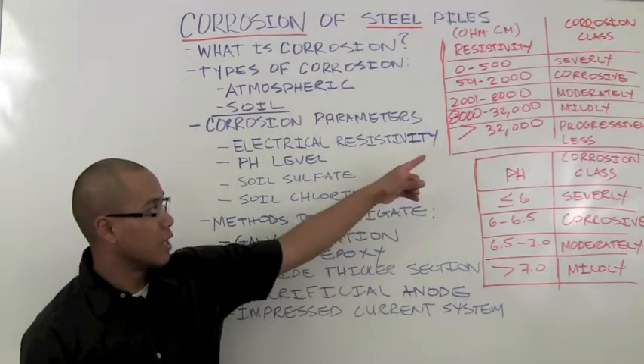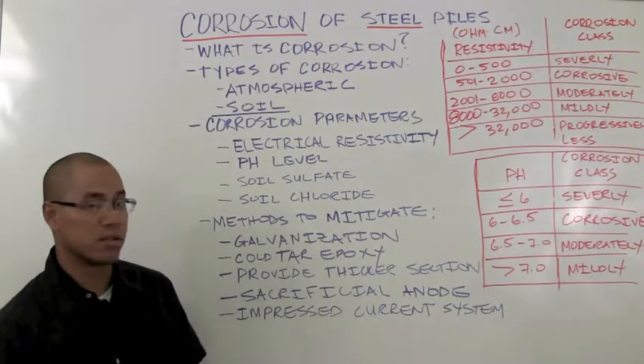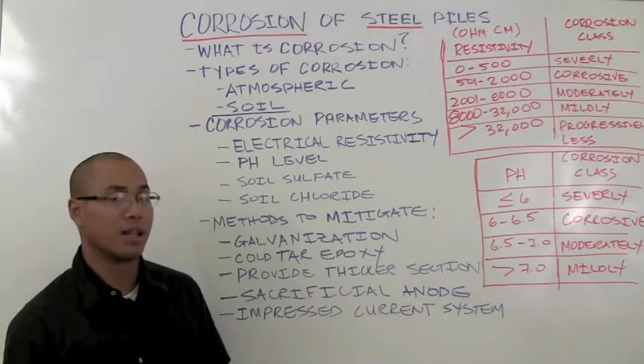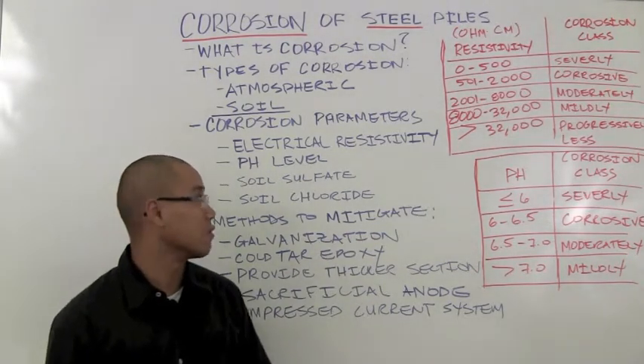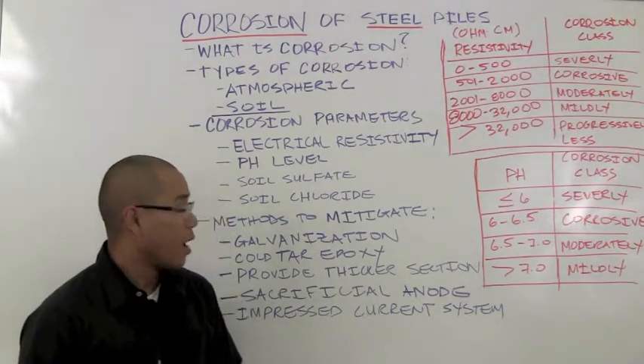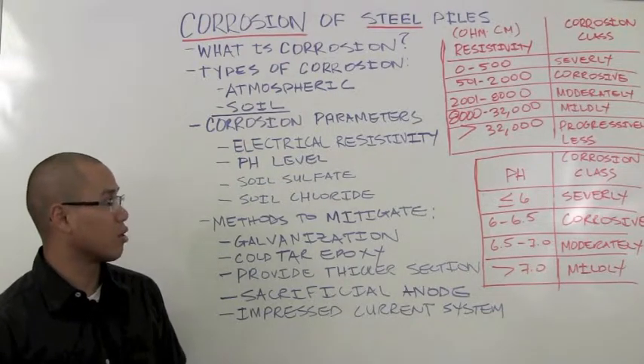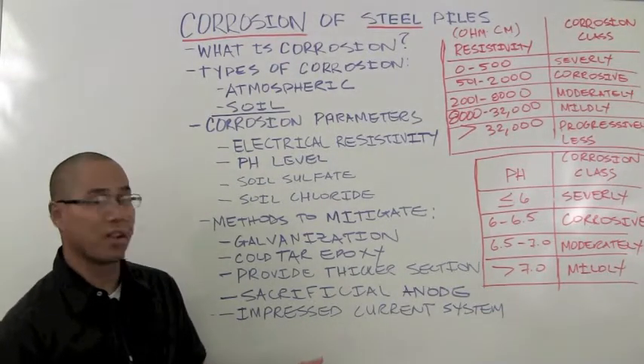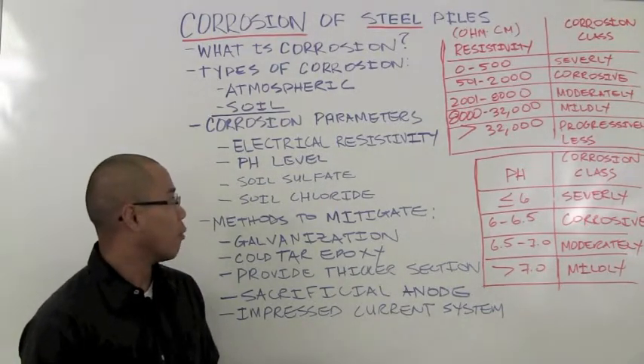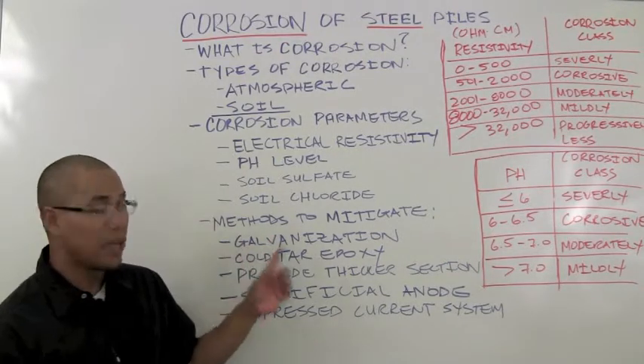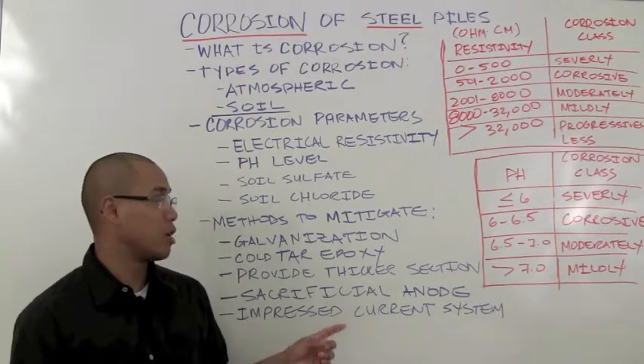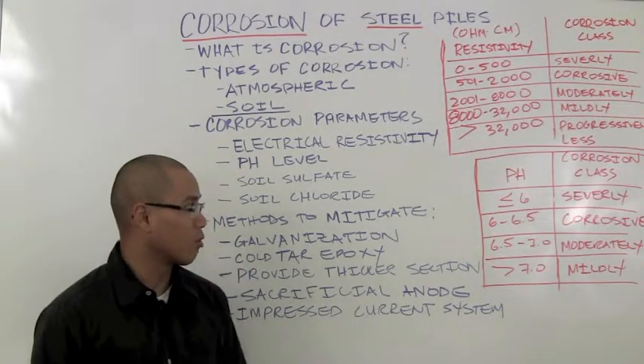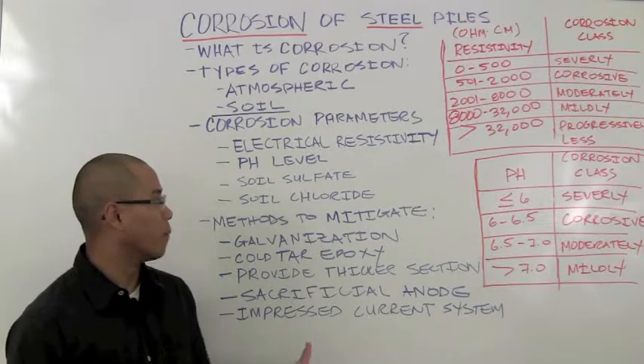As you can see, anything above 32,000 ohm centimeters, the soil is deemed to be progressively less corrosive. However, if the piles are to be coated or galvanized with zinc, pH also plays a major role in corrosion rates.